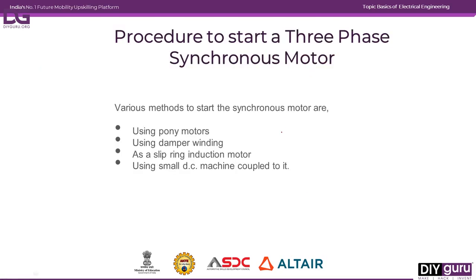After starting, we can remove the external device and the rotor will rotate at synchronous speed on its own. There are several methods to start the synchronous motor: using a small auxiliary motor, using damper winding (along with the actual rotor winding), using a slip-ring induction motor, or using a small DC machine coupled to the shaft of the synchronous motor.